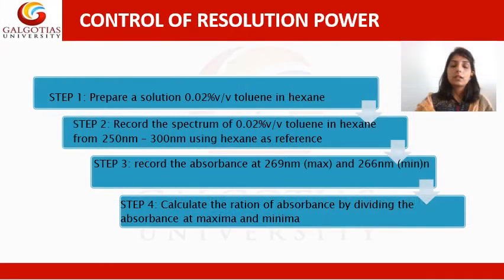Then comes the control of resolution power. For that you will prepare a solution of 0.02% volume by volume toluene in hexane. You will record a spectrum of 0.02% volume by volume toluene in hexane from 250 nanometer to 300 nanometer, in which you will use hexane as your reference. The absorbance you will record at 269 nanometer and 266 nanometer. This is your lower wavelength, this is your higher wavelength, and then you will calculate the ratio, that is maxima divided by minima. Whatever absorbance value you get at 269 nanometer, you will divide it by the value you obtain at 266 nanometer and find the ratio.